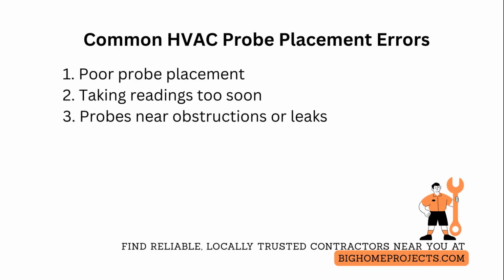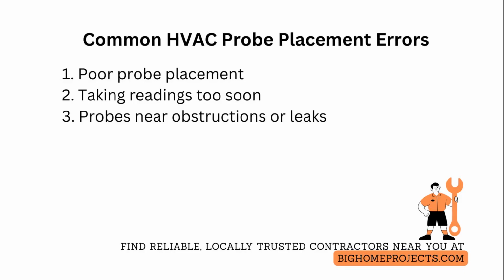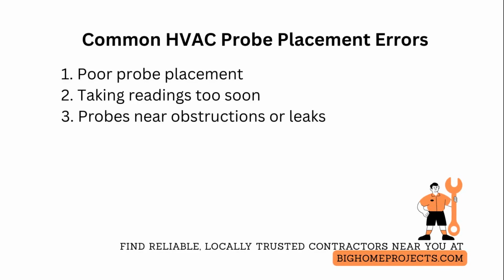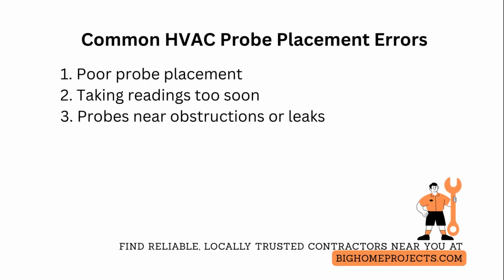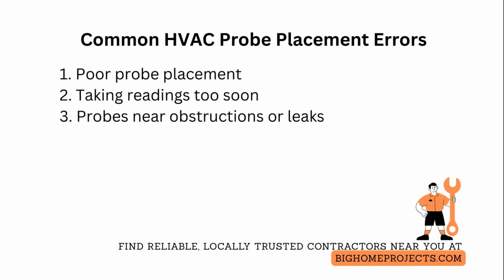One of the biggest mistakes is poor probe placement causing inaccurate HVAC temperature rise readings. Fix it by moving the return probe adjacent to the air handler plenum and the supply probe downstream of the coil, but out of direct radiant view. Seal both probes in drilled ports and retest after system stabilization.